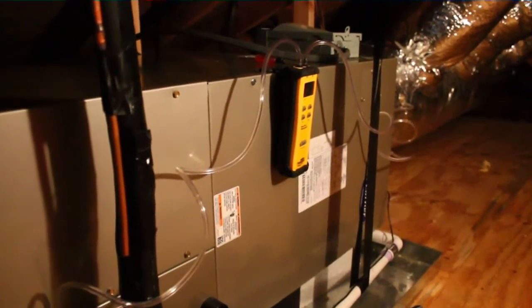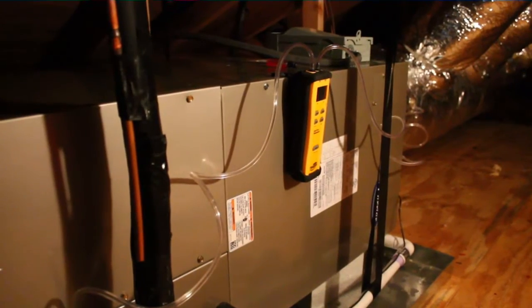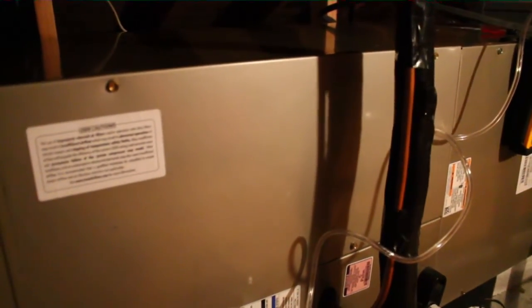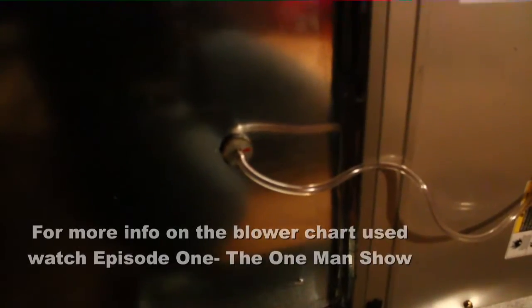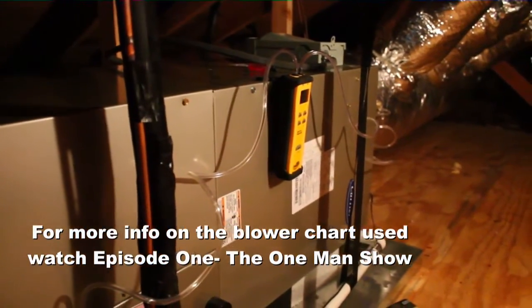It's 0.54 to 0.56 static, about the exact same as the last job we did, the one-man show job. So our CFM numbers are gonna be about the exact same, between 900 and 1,000, depending on if regular heat or emergency heat's running. So we're gonna let this run. The vacuum's going outside. Start packing up some trash, and then we can start things up whenever the vacuum gets done.